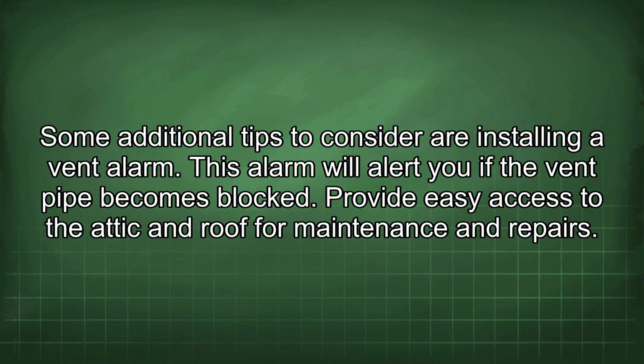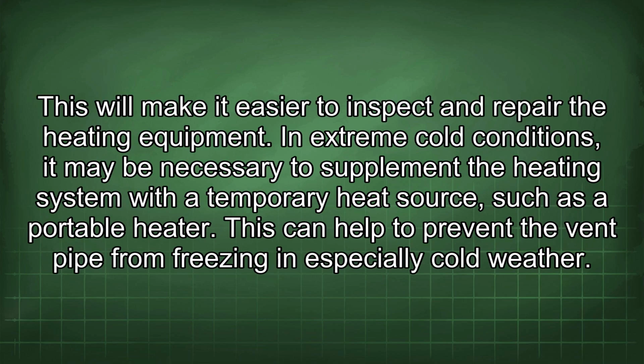Some additional tips to consider are installing a vent alarm. This alarm will alert you if the vent pipe becomes blocked. Provide easy access to the attic and roof for maintenance and repairs. This will make it easier to inspect and repair the heating equipment. In extreme cold conditions, it may be necessary to supplement the heating system with a temporary heat source such as a portable heater. This can help to prevent the vent pipe from freezing in especially cold weather.